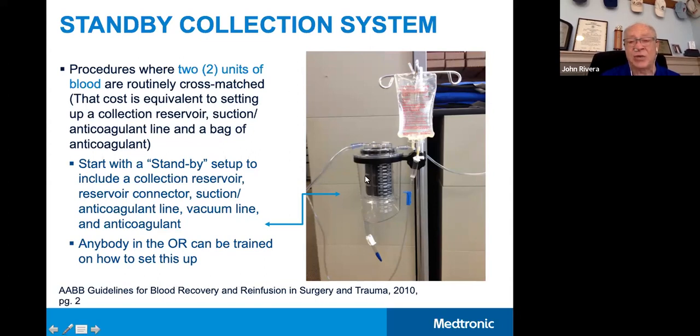And in this case, this reservoir is 4 liters in volume. They generally start at 2. And with the filter that's on there, that's a gross filter. I know it's 120, but the filters can be as gross as 180 microns, but as fine as 20 microns. 20-micron reservoirs are used primarily on surgery of brain tissue because brain tissue is so thromboplastic.